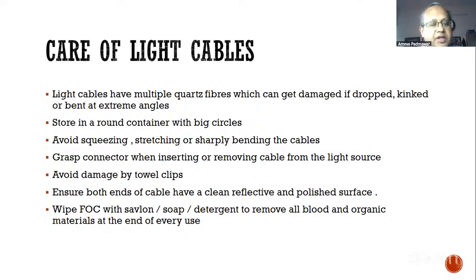Whenever you are fastening it with other cables over the patient's legs or the abdomen, always use a gauze piece to tie all the cables together and then put a clip on it to fasten it to the drapes, but do not use a clip directly on the fiber optic cable. Ensure that both ends of the cable are clean so that the light transmission is maximum through its reflective and polished surface. At the end of the surgery, wipe it with a soap solution and remove all the blood and organic materials at the end of every use.